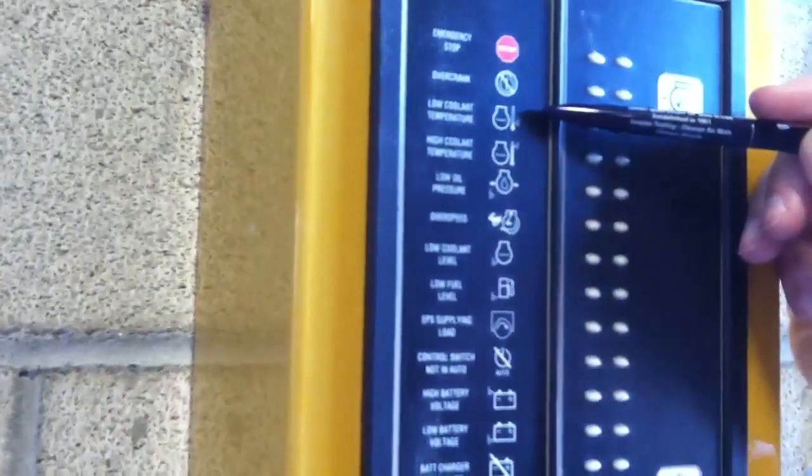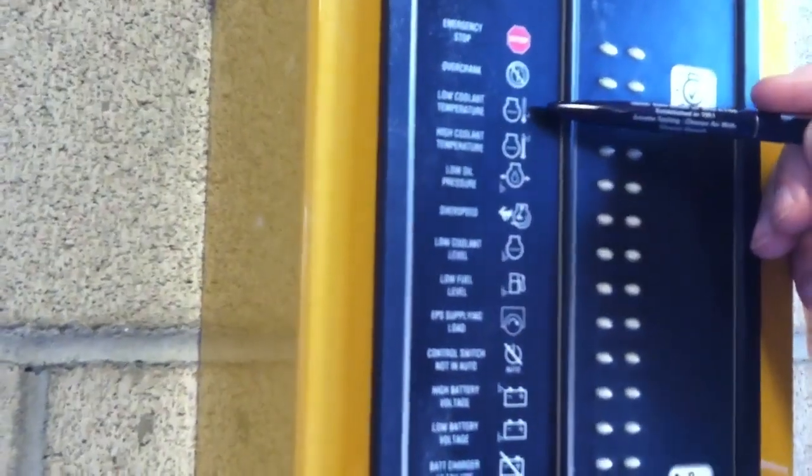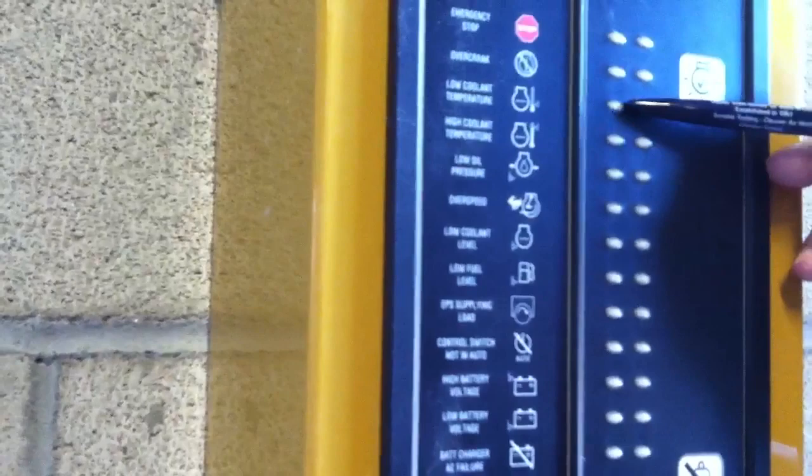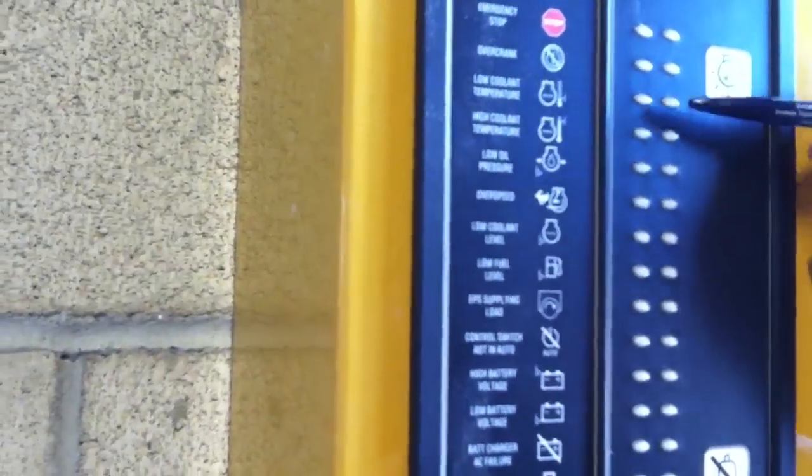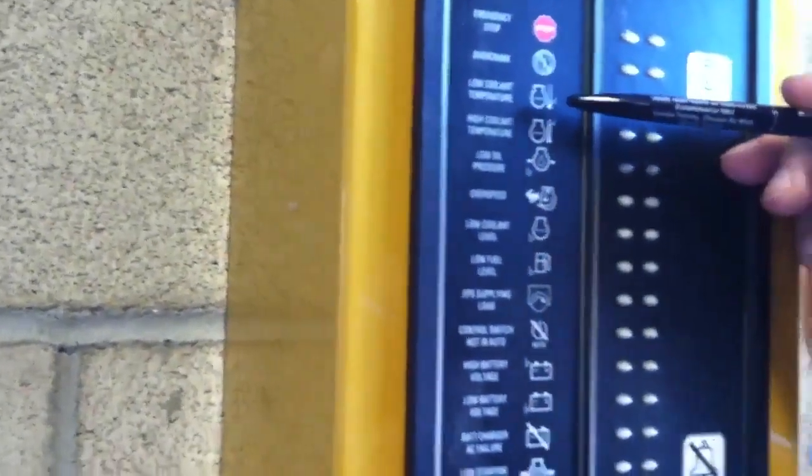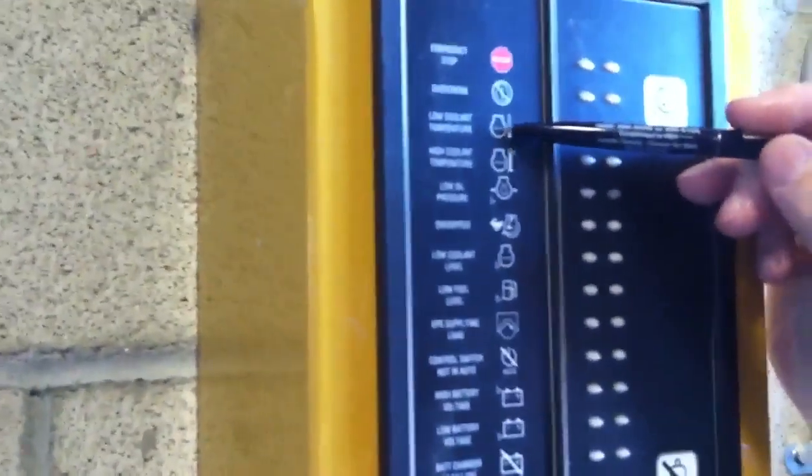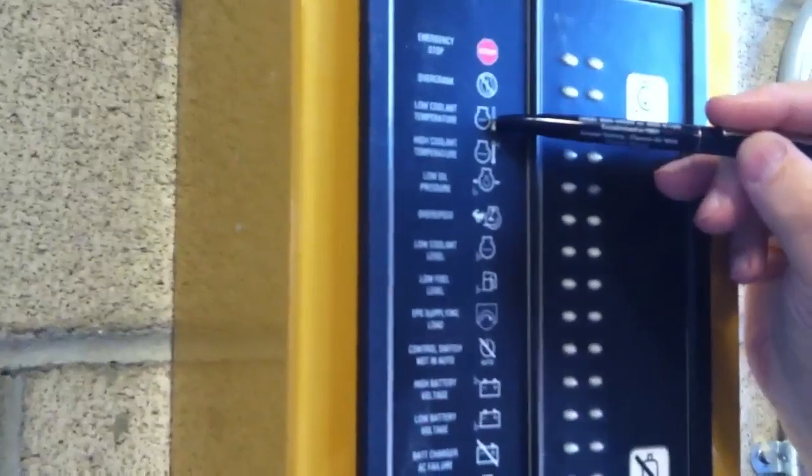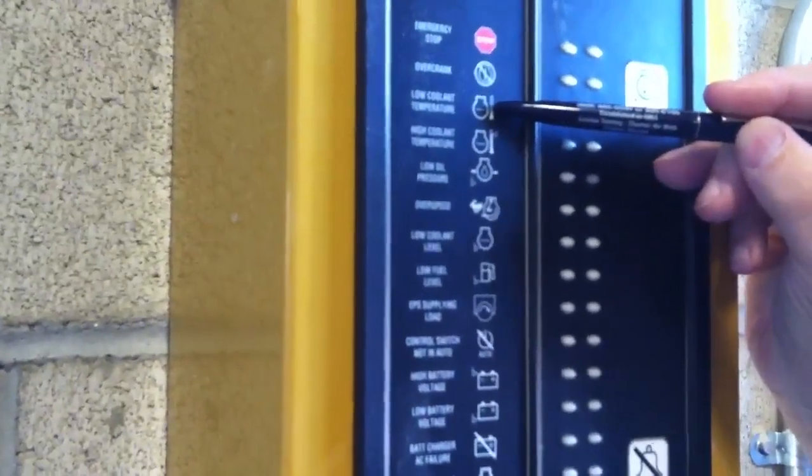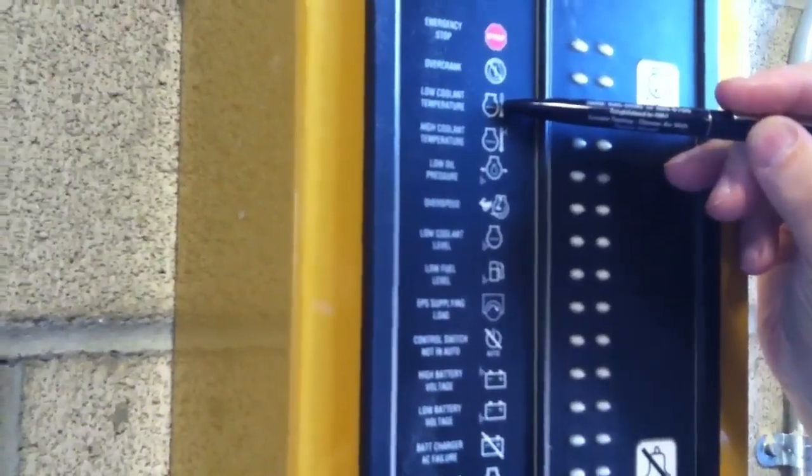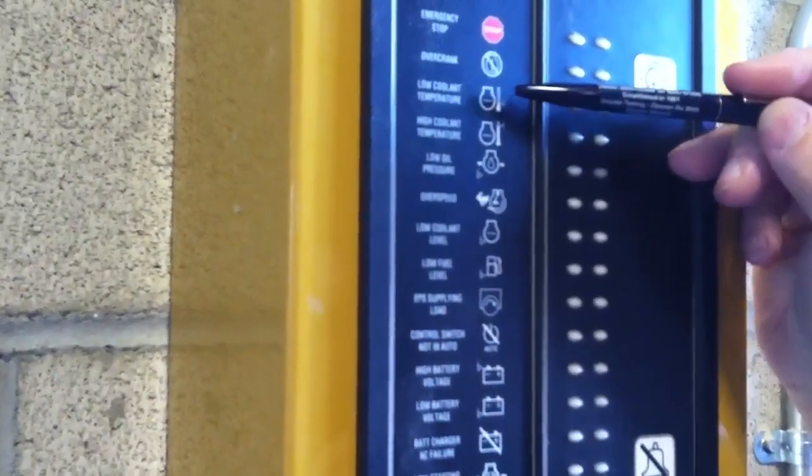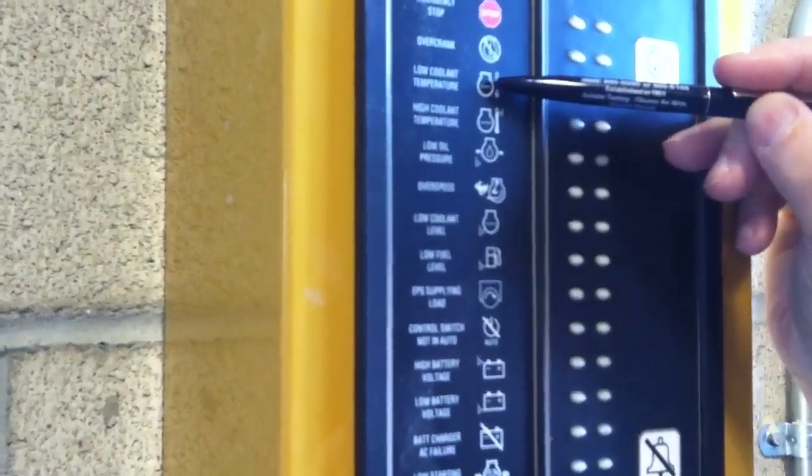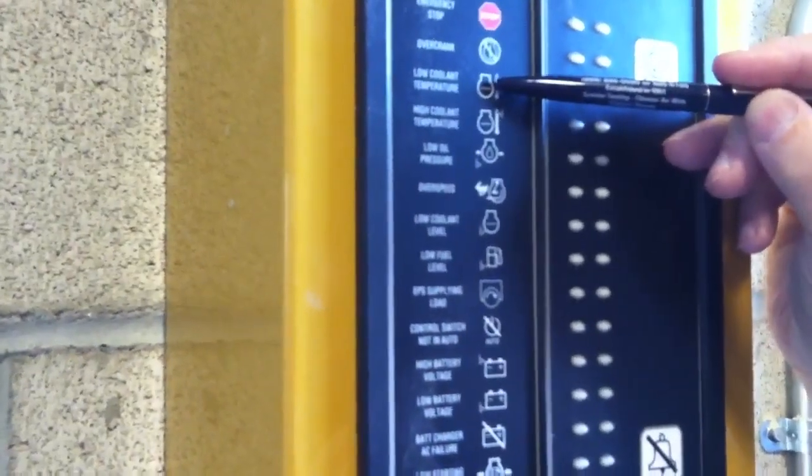Low coolant temperature is not a shutdown however it's a warning. We're going to get it over here and what that is is if we drop below 70 degrees and that heater we have on the engine is going to keep that above that. Then we've either had a trip breaker on the heater or the heaters fail.